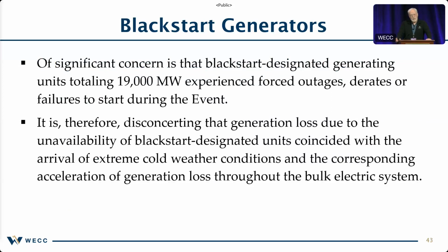Black start generators. So black start generators are those generators that are capable of starting without having any power source from the power system. During an emergency, like maybe a winter storm moving into your area where you're losing a lot of generation and you run the risk of having a blackout, you want to have black start resources. It's an integral part of a system operator's restoration plan.